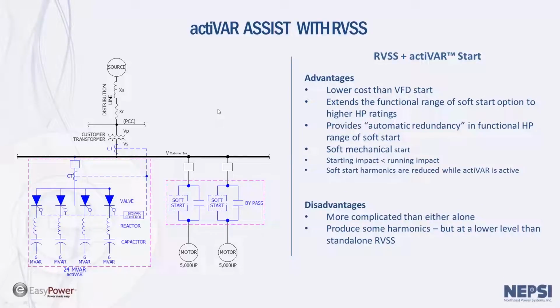So the actiVAR can also be used with a reduced voltage soft start. This slide shows that here, where the soft start will start to operate and the actiVAR will supplement the soft start. This is particularly useful in the higher horsepower range, for example, even at 5,000 horsepower, 6,000, 7,000 horsepower, where a soft start cannot perform the function and typically would force you into a VFD drive. In this situation, the actiVAR can be used to supplement the soft start. In addition to supplying reactive power for a soft start to help support the voltage, it will also help reduce the harmonic current during the starting period.